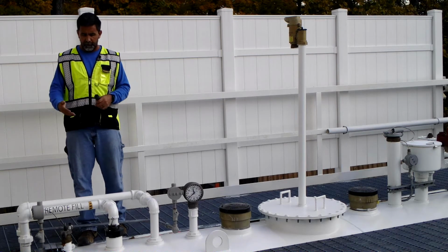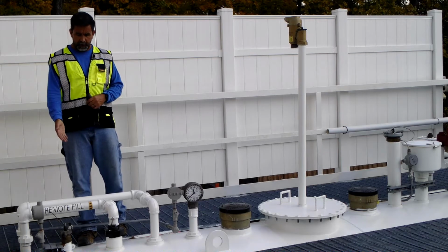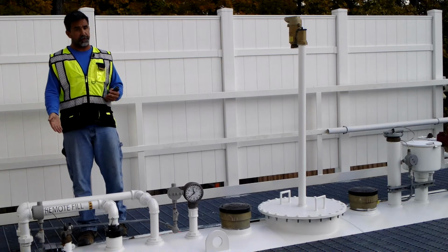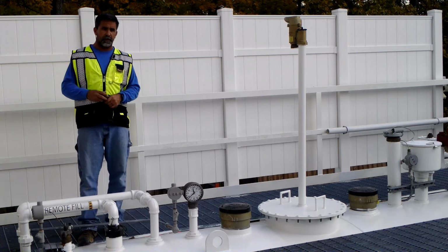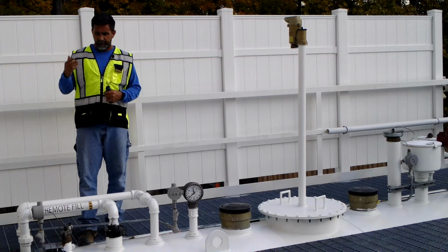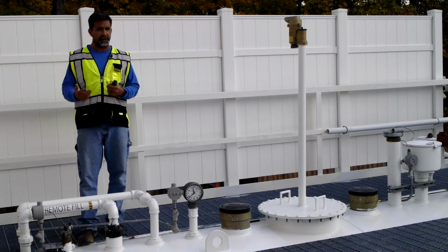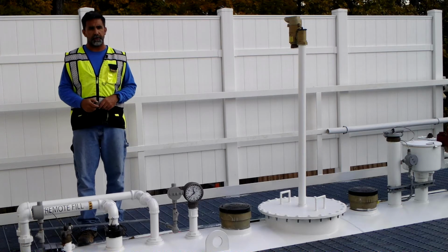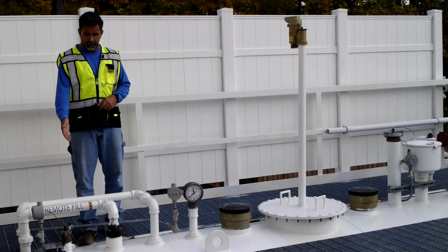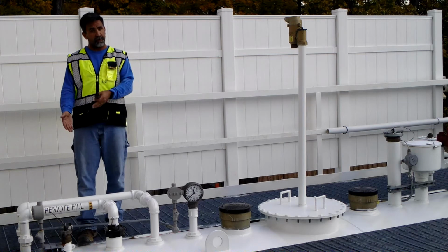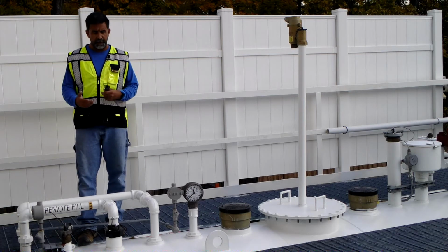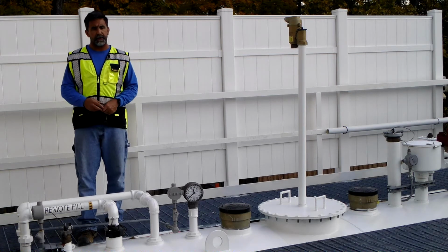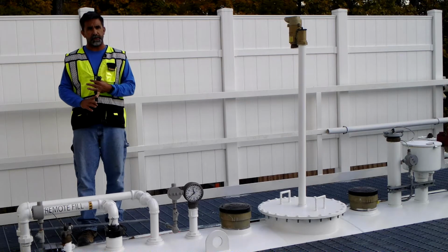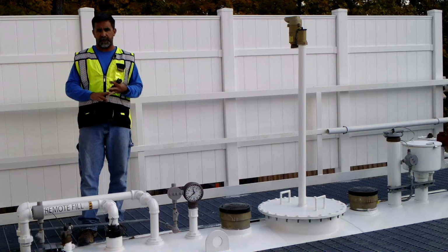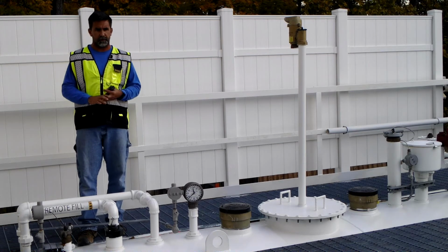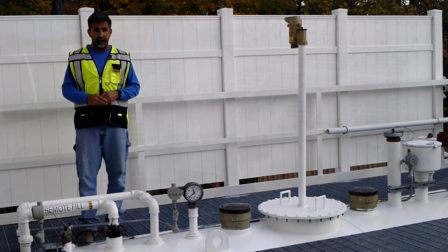After you've performed that, and everything looks good, go ahead and put the sensor back into the interstice. Sometimes there's a float with just a little level indicator. Either way, return it back to the condition that it was in before you started your inspection. Resecure and relock the cap to prevent any water from getting in, and then you're done with inspecting the secondary. You verified that there is or is not the presence of water, and you've checked to see if the indicator, the float, or the sensor is functional. Now let's take a closer look at this.